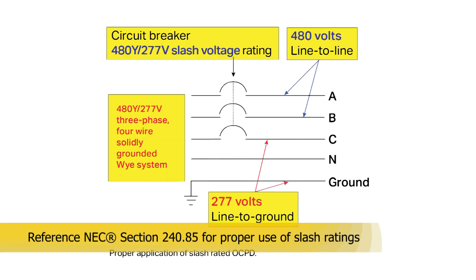Multiple pole mechanical overcurrent protected devices with a slash voltage rating, such as circuit breakers, self-protected starters, and manual motor controllers, are limited in their application and require extra evaluation for use. The slash rating can be broken down into its higher and lower numbers. The lower rating pertains to overcurrents at line to ground voltages, intended to be cleared by one pole of the device. The higher rating number pertains to overcurrents at line to line voltage, intended to be cleared by 2 or 3 poles of the device.